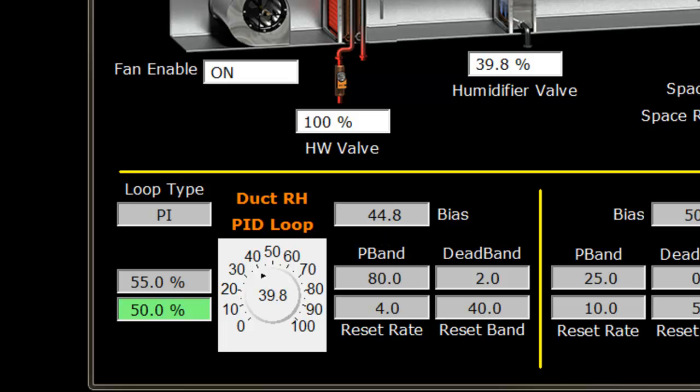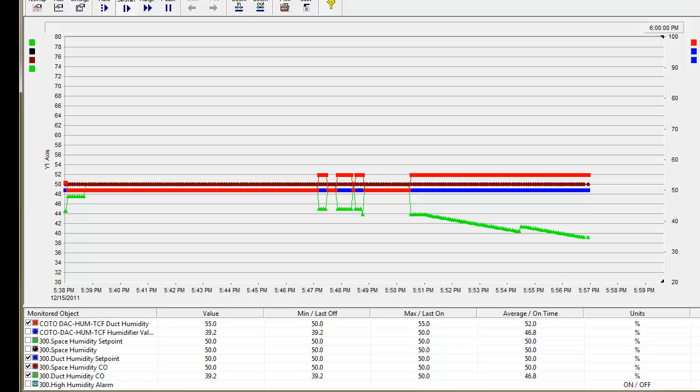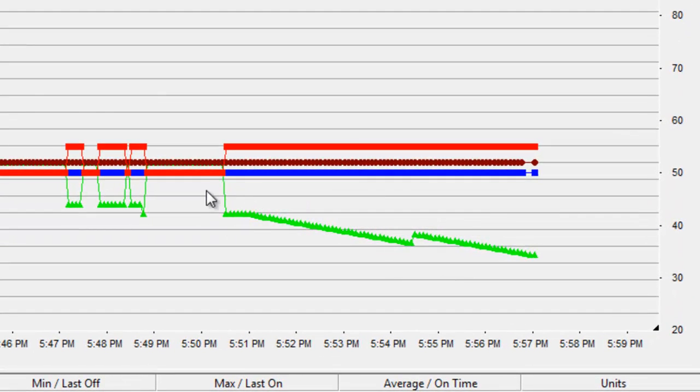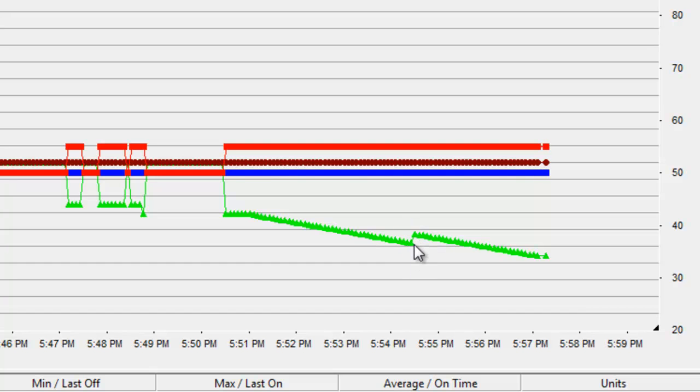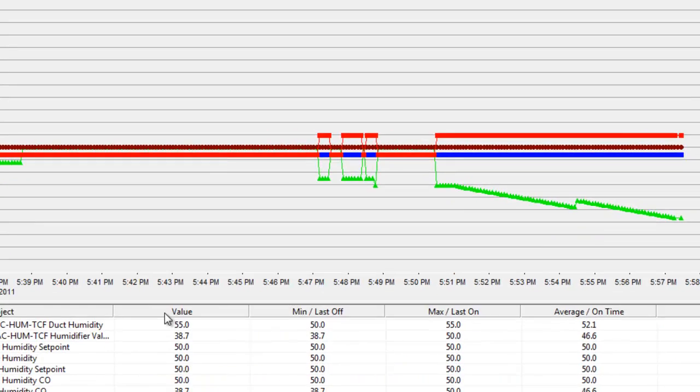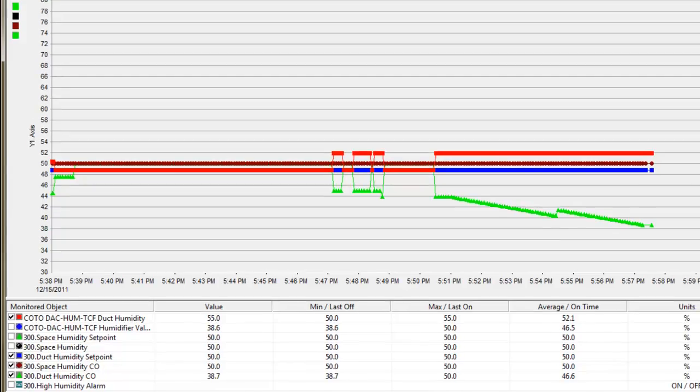I've got this graph here. If we look at it, we began talking and I adjusted to a PI loop, which made a big jump, and it began to continue adjusting, trying to go lower. This little tick mark is when I set the dead band change from 0.2 to 2. That was that little jump there. As we continue to talk, it continues to take down, waiting to adjust the duct humidity, which is the red symbol.